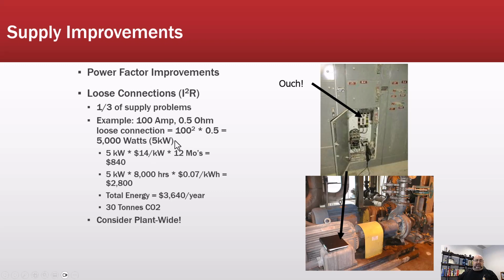Let's take a look at a ridiculous loose connection, because we would probably be burning the plant down. But loose connections make up about 1/3 of supply problems. As a matter of fact, loose connections in a system make up about 0.2% of the energy cost improvements, or can reduce your cost by about 0.2%. So an example: say I have 100 amps at a 1/2 ohm. Now I-squared-R works whether I'm talking about AC or DC. That would be 100 squared amps times 0.5 ohms. That's 5,000 watts or 5 kilowatts. And if I start calculating that out, I come up with $3,600 a year and 30 tons of CO2.